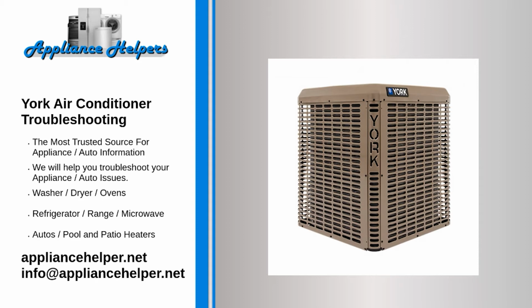Clean or change the filters, no matter your model. Always start by installing a new filter for disposable types, or cleaning the filter for permanent types. Clean condenser coil surfaces after filters. Dirt should be cleared off the condenser coil to restore the required operation.